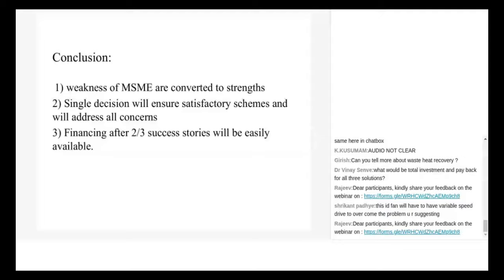So waste heat recovery is actually a long topic. If it's 400 degrees centigrade, you have a host of options, like whether you go for a hot oil unit. It depends on exactly where they want to use it back. Normally air preheating is the first option that comes in. Other options arise when steam generation isn't involved, because steam and water go together, whereas air and combustion equipment go together, like in metallurgy, since there's no water vapor generation there. So if it's waste heat recovery alone, it can be in air form.